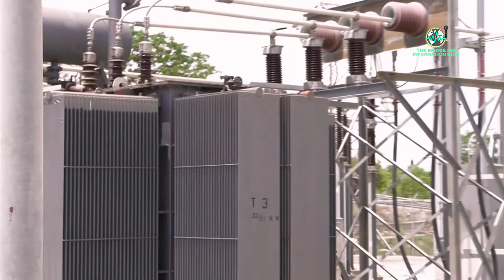We have a lot of projects in the Shiroro sub-region. We have done SSC projects, one of which is the installation of a 330/132 kV CB on Kaduna Line 1. The bulk supply that goes to Kaduna town comes from Shiroro through this line, so it's a very critical line we need to keep in operation. Line 1 in of Abuja 2 was out for a long time, during which we were able to replace all the lightning arresters there. This was a critical job we did at the time.